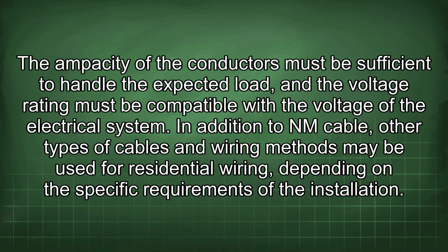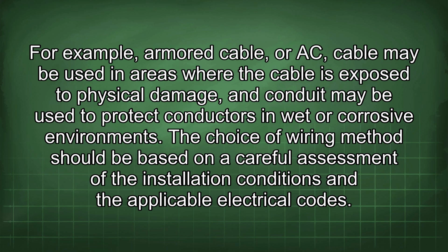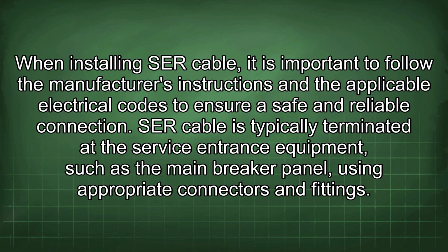In addition to NM cable, other types of cables and wiring methods may be used for residential wiring depending on the specific requirements of the installation. For example, armored cable or AC cable may be used in areas where the cable is exposed to physical damage, and conduit may be used to protect conductors in wet or corrosive environments. The choice of wiring methods should be based on a careful assessment of the installation conditions and the applicable electrical codes. When installing SER cable, it is important to follow the manufacturer's instructions and the applicable electrical codes to ensure a safe and reliable connection.